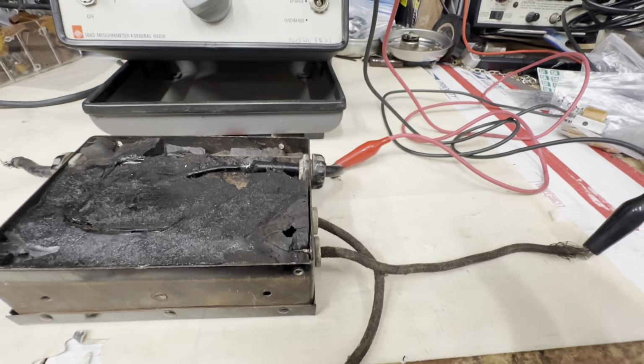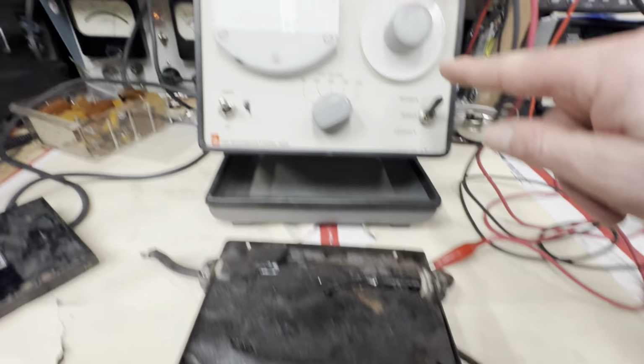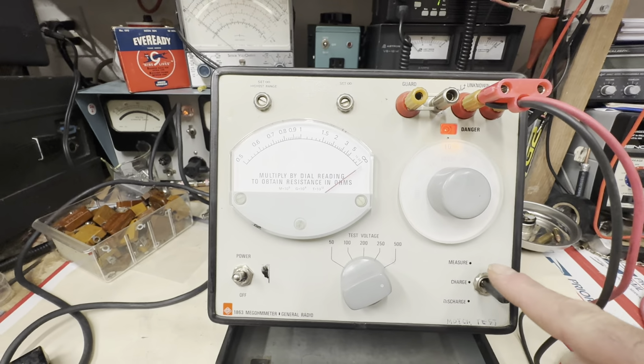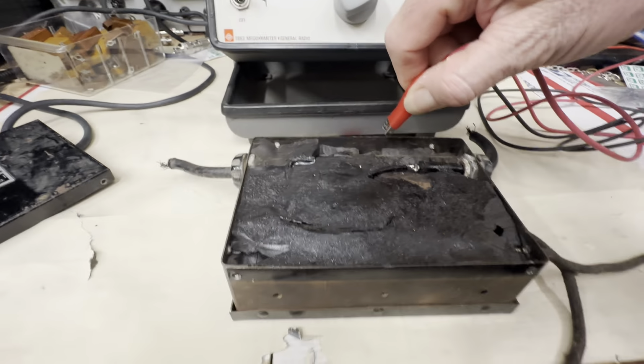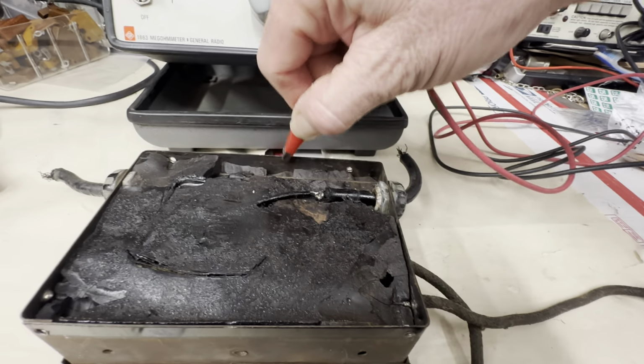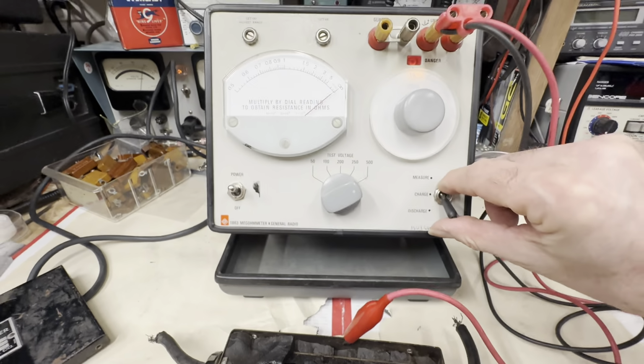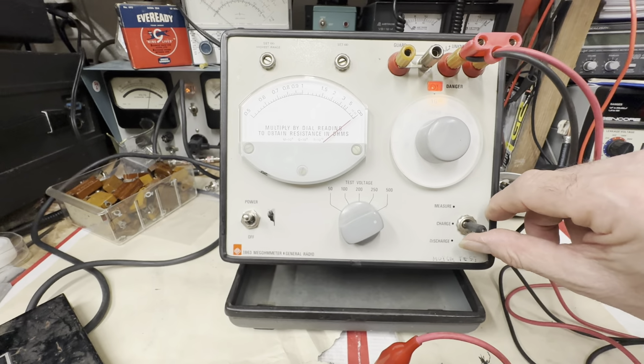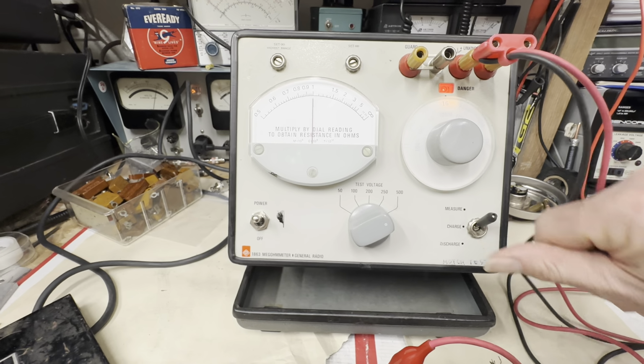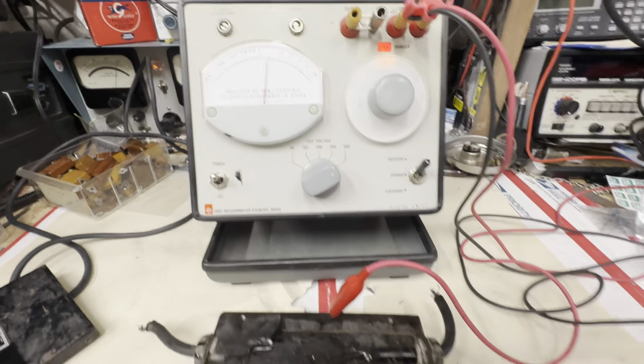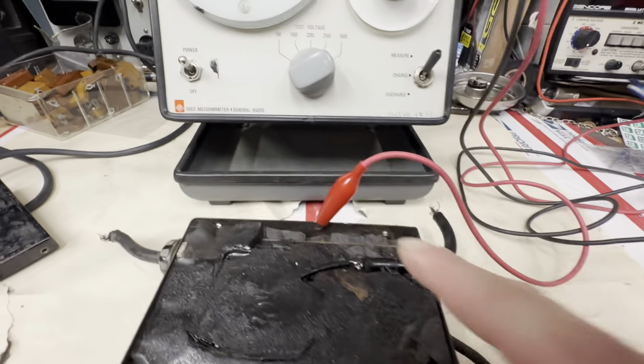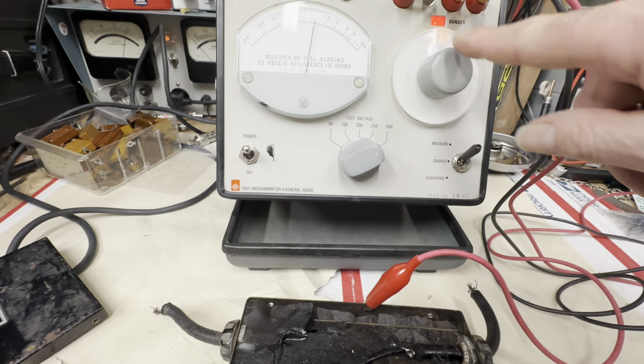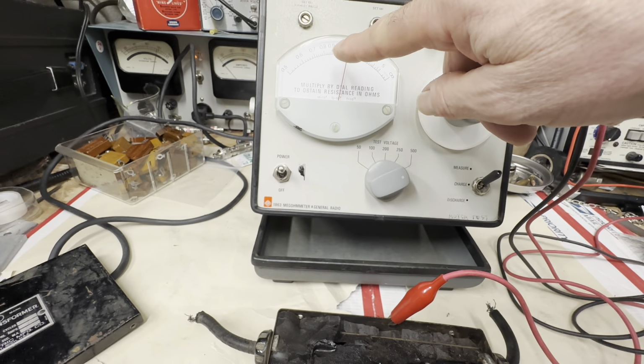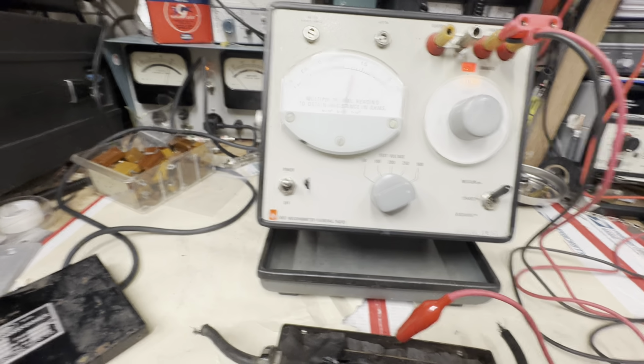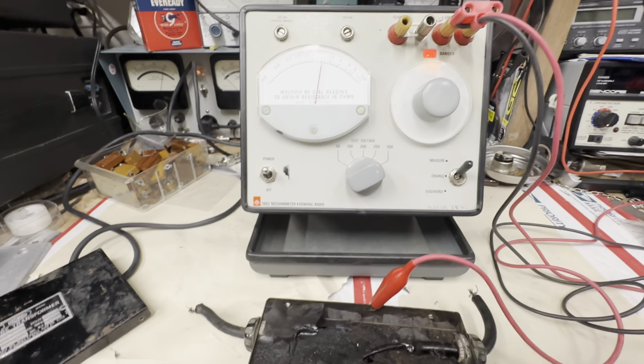Let's check and see what the different windings are to ground. Okay, we're going to switch to safety, turn this off, and now what we're going to do is take the input here at the 110, and we're going to go to ground, kick it back on again, and that one quick blip as it charged, and there we go. And right now, 110 volts to ground. And right now, we're looking at 1 gig. So that's 1 gig, 1.2 gigs. That's perfectly fine. No worries at all with that.